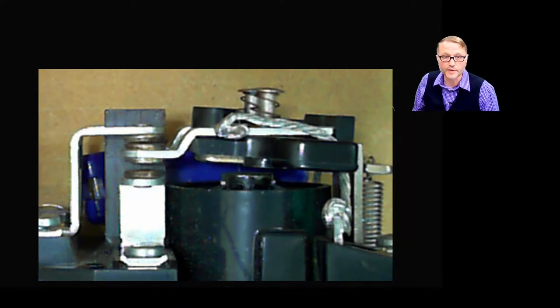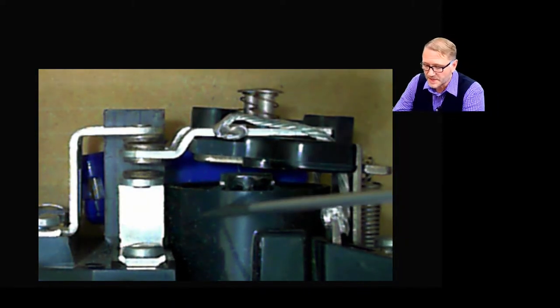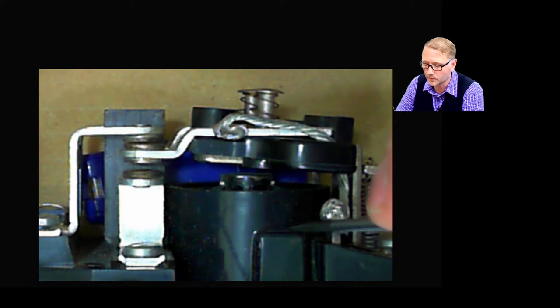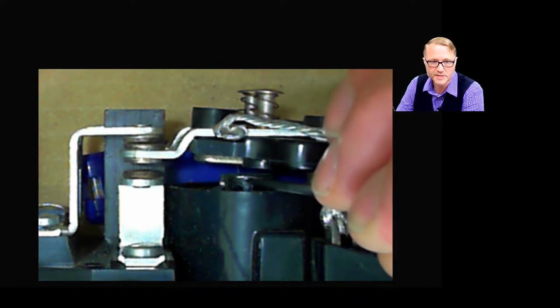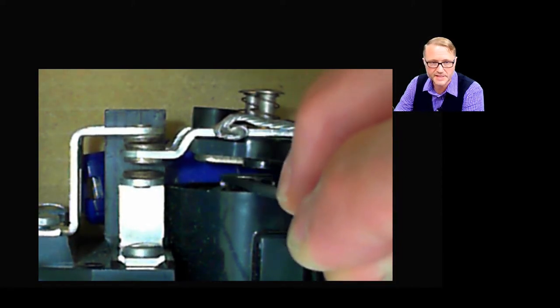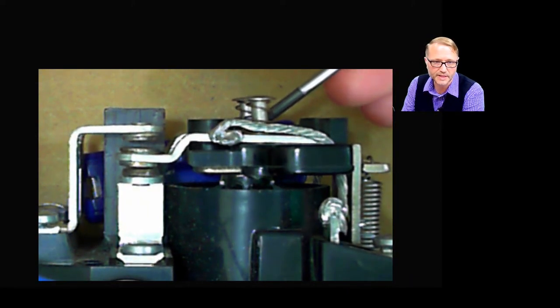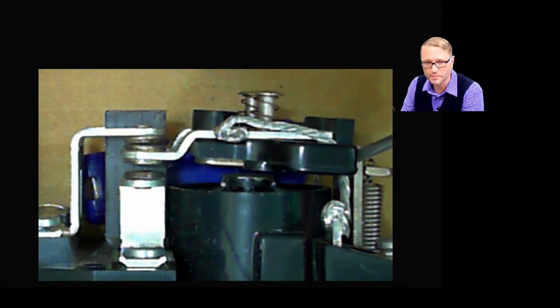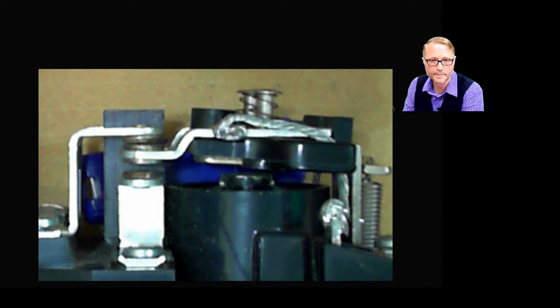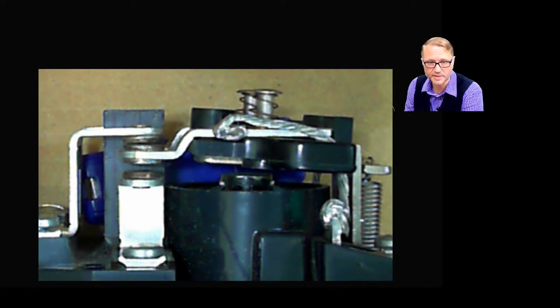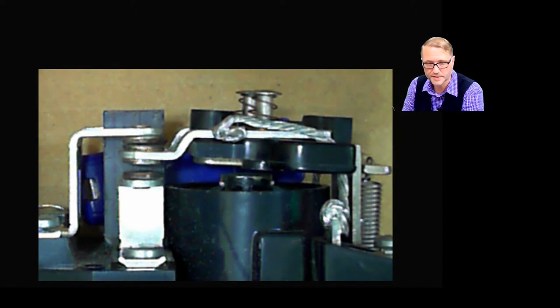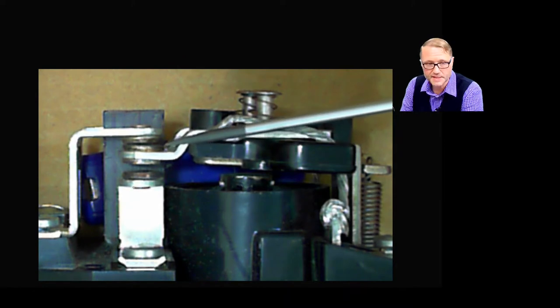What I'd like to do next is explore the components of a control relay. This here, this large black cylinder, is the electromagnet. Coils of wire are wound around a central core. You can see the core right here. The magnetic field is concentrated on that core, which will pull against the metal in the armature. So here is the armature moving. If the coil was activated, it would be pulled like so. Can you see the pivot point back there? And there's also a spring that pulls against the armature and keeps it in place. So again, coil, armature, the pivot point, and the spring.